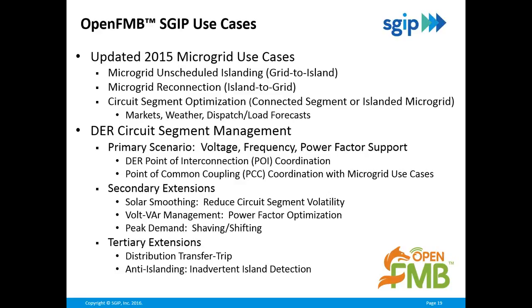So in this case, we'd expect your reclosers and switches to detect anomalies and losses of power, but when you have too much solar and bidirectional power flow, you may not see that fault. In that case, you'd have a third use case that provides a tertiary measure to ensure the fault was identified and shared across the message bus and all the different reclosers on that power system.